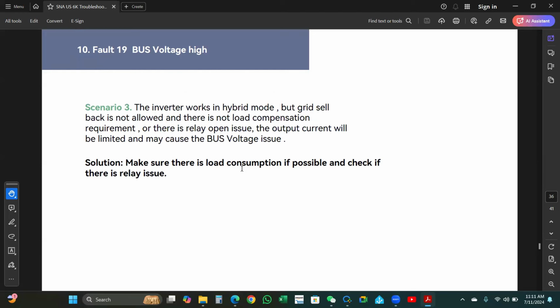Scenario number 3: the inverter works in hybrid mode, but grid sellback is not allowed, and there is no load compensation requirement, or there is a relay open issue. The output current will be limited and may cause a bus voltage issue. Solution: make sure there is a load consumption if possible, and check if there is a relay issue.